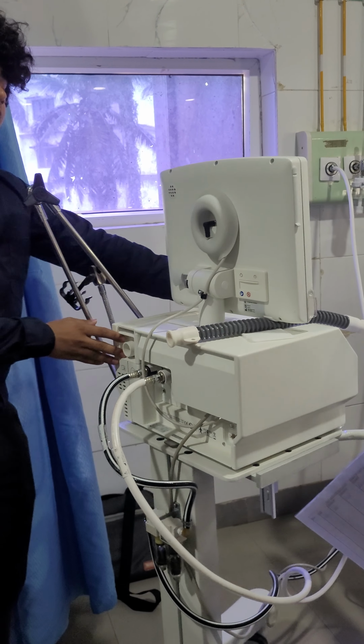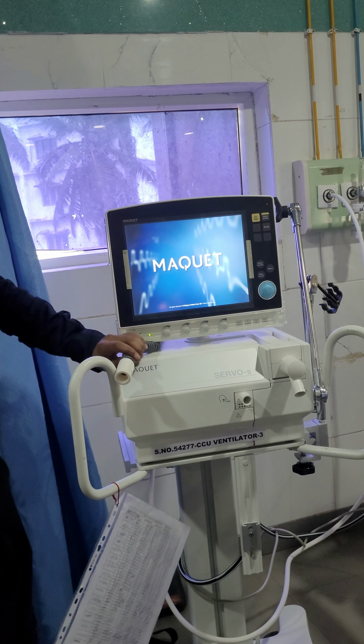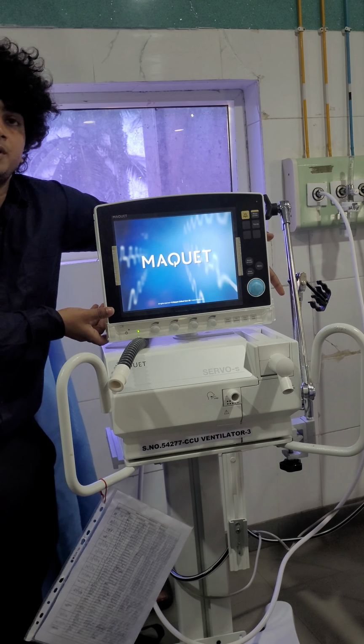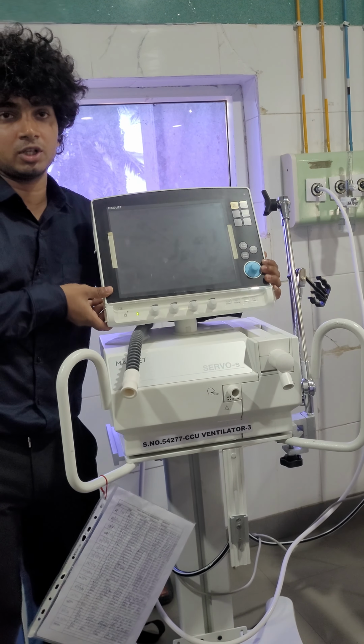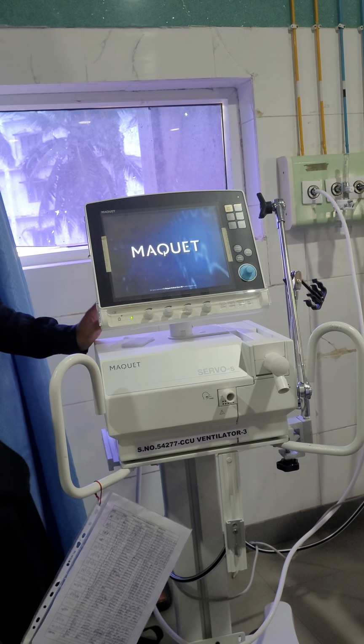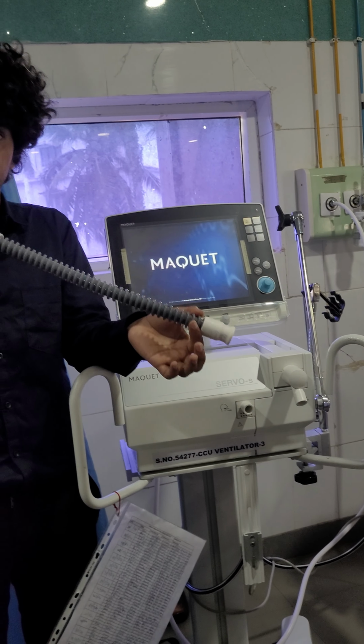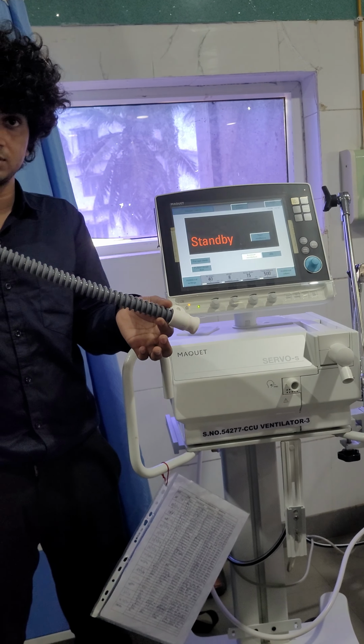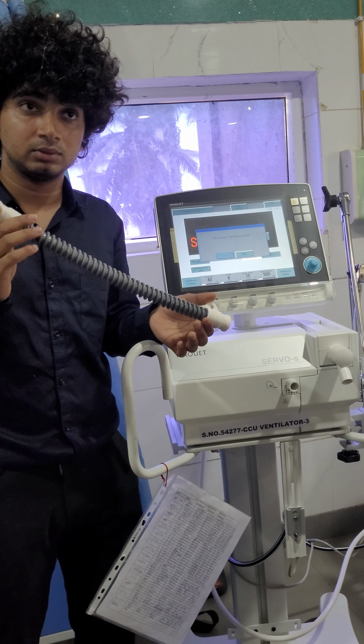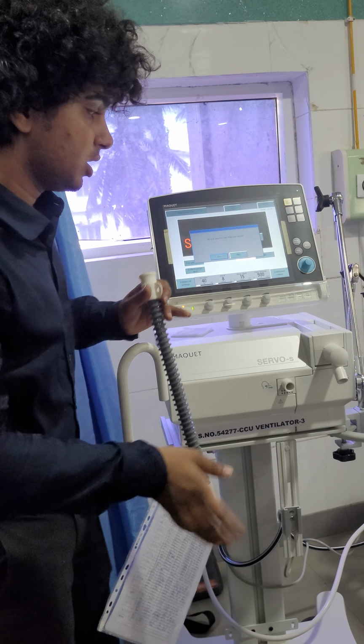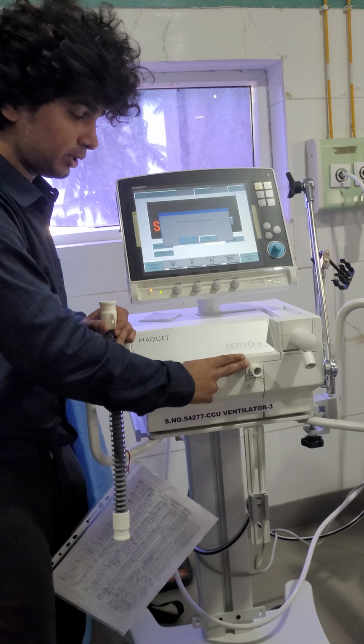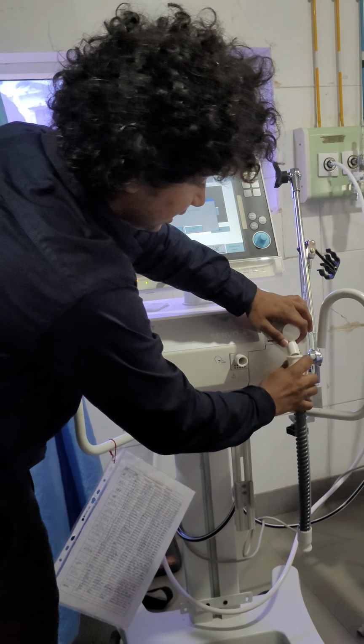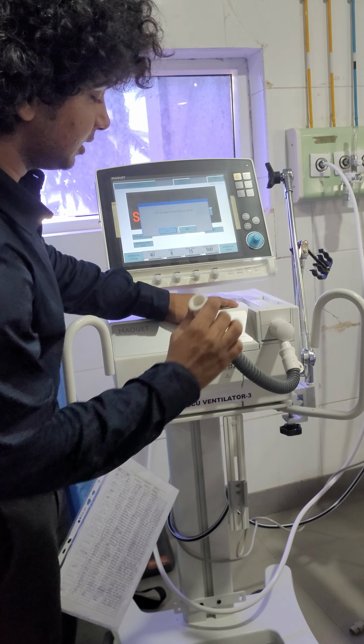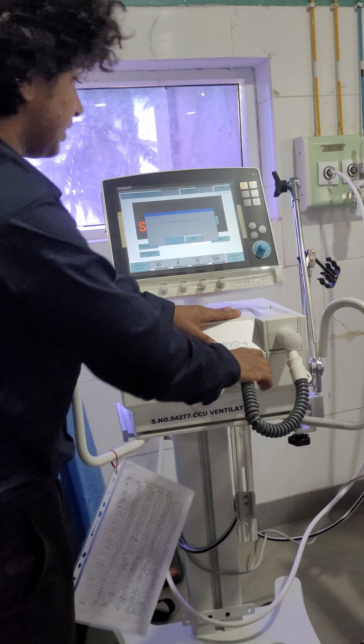After turning on the ventilator, do the pre-use check before connecting it to a new patient. For the pre-use check, this is the tube you have to use. This is the expiratory side, this will be the inspiratory side. I will connect one end to the expiratory side and the other end to the inspiratory side.